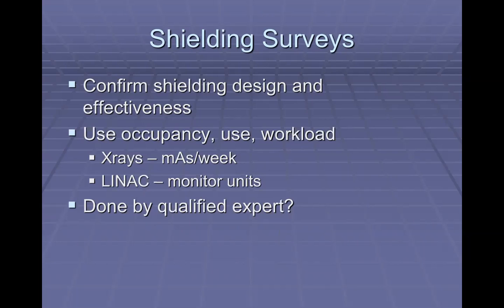But if you do that enough, you get some void spaces that can unfortunately not be shielding. And so when that's built, you're doing your survey and you get hot spots, and it's like, okay, well, why is that? This was designed right, and it's okay, well, it wasn't implemented to the design. So there's a million reasons why your design can fall short, why during construction your design doesn't pan out 100%.